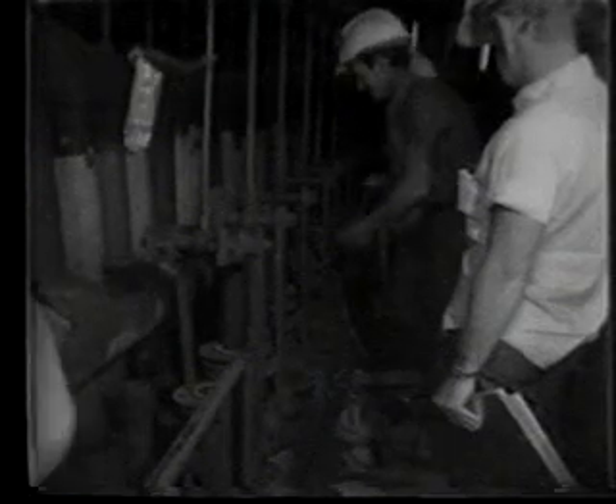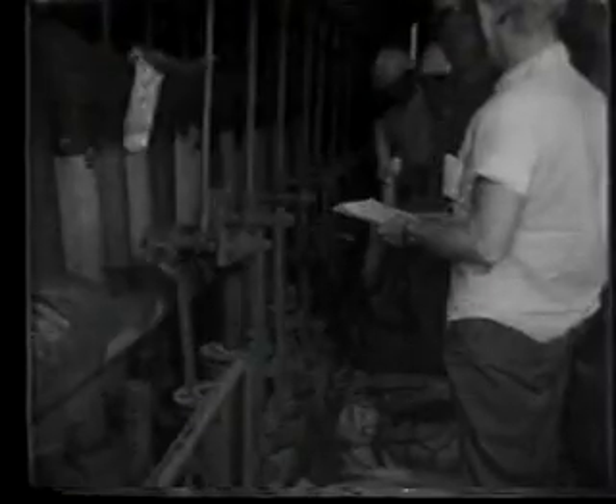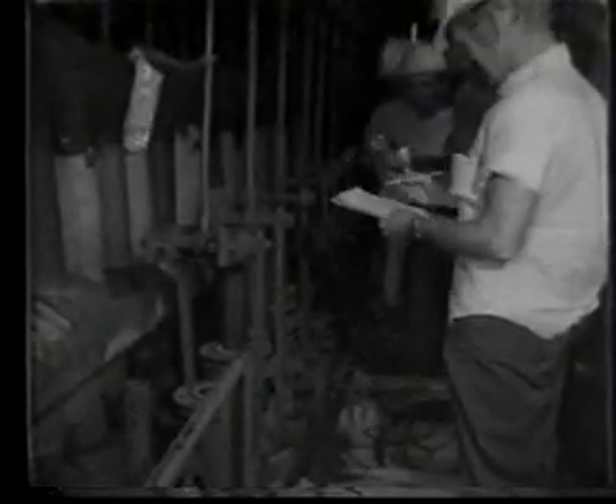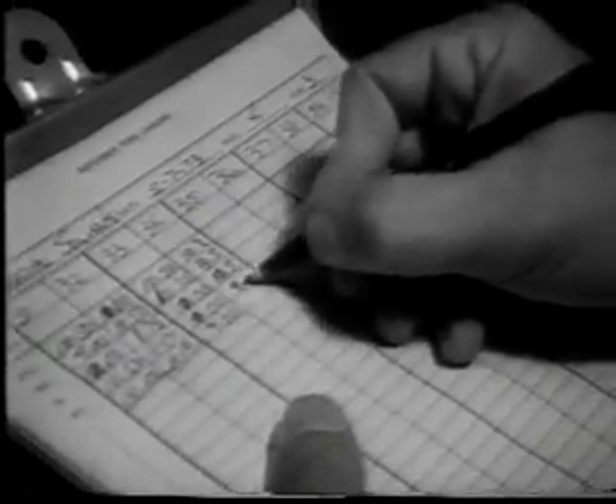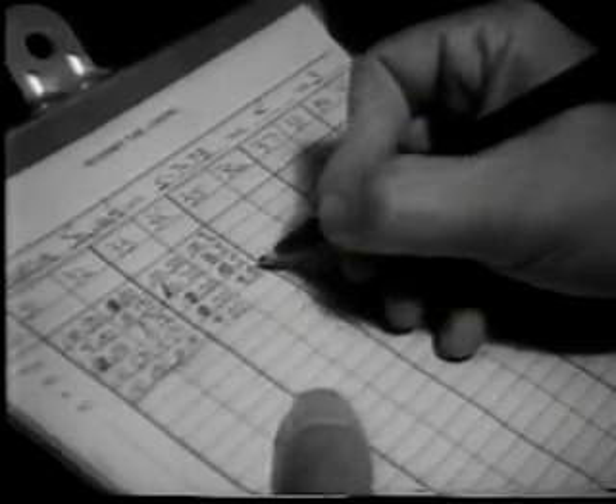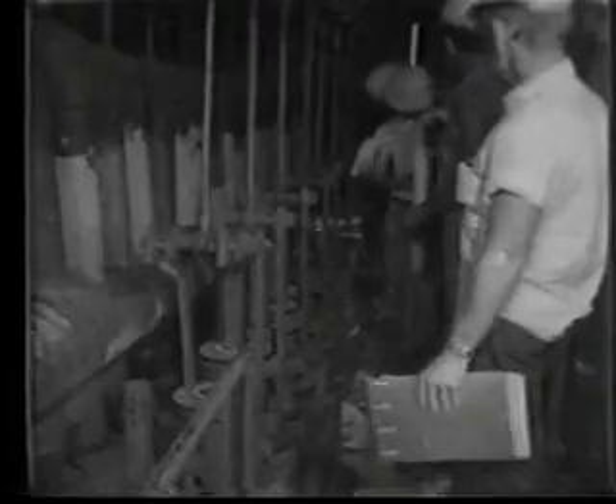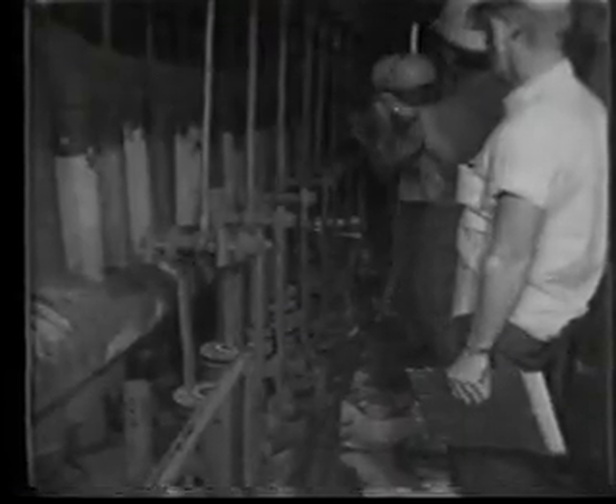Also, there is always a difference in the way the catalyst settles in each reformer tube. You might get 7 full bags in one tube and only get 6 1/4 in another. So, when loading the tubes, always carefully measure, calculate, and correct the loads in each tube individually. We strive for perfection on every job. This keeps our customers satisfied.